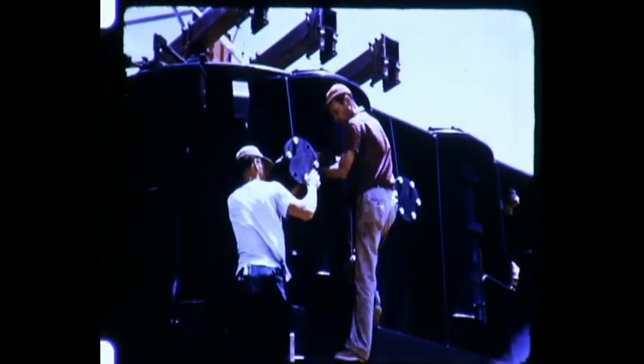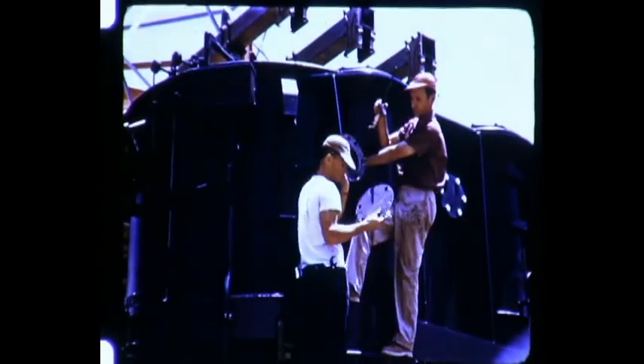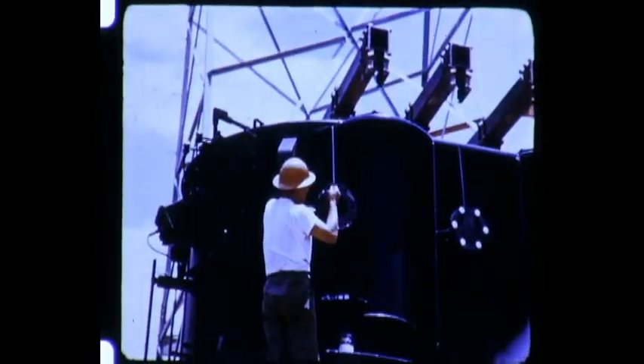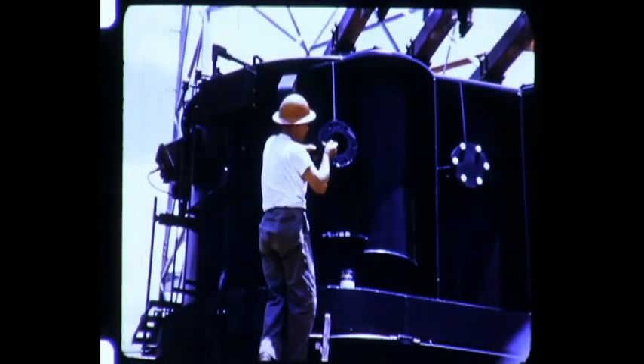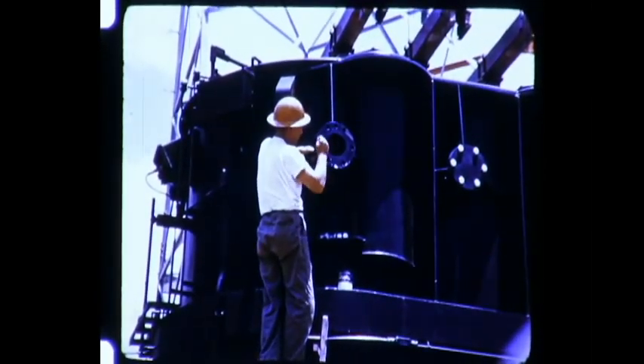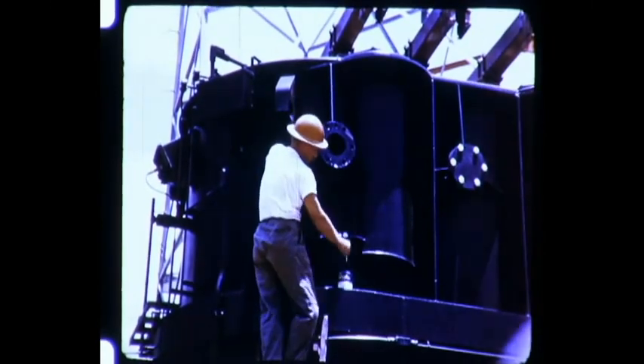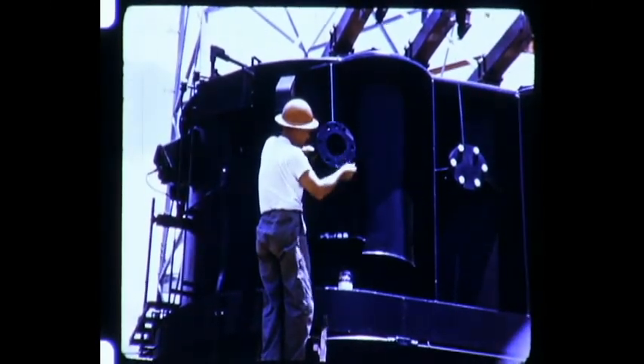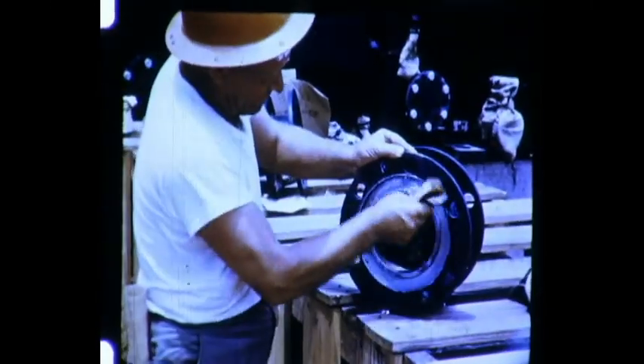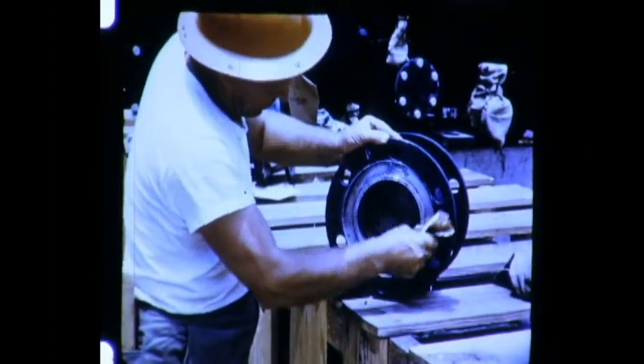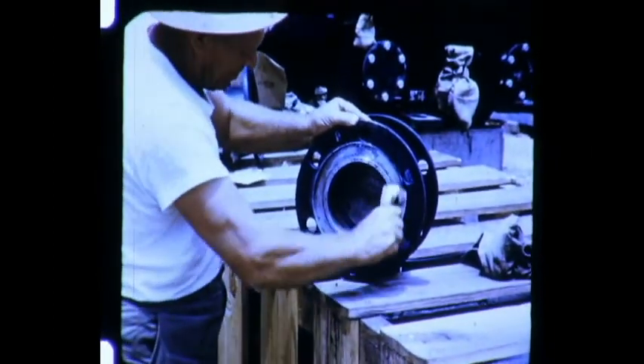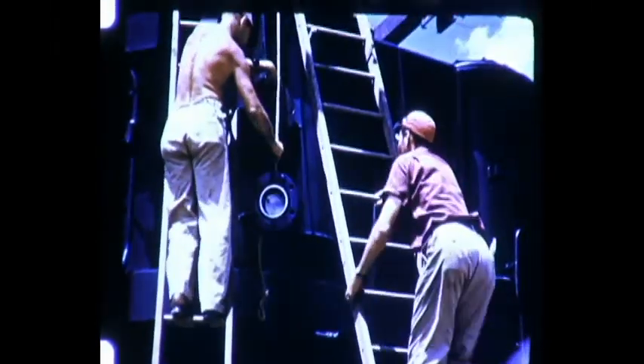After venting the tank to relieve gas pressure, a shipping cover is removed to make ready for the upper shutoff valve to which the first cooler will be mounted. Cleaning the gasket surface assures an oil-tight connection. Oil-proof Glyptal paint is used for retouching the flange except where it will be in contact with the gasket. The upper valves in this case were shipped separately to meet railroad clearances. Gasket surfaces are rubbed clean before the valve is raised and bolted to the flange.